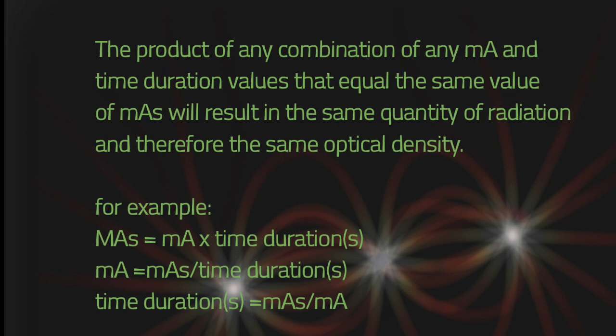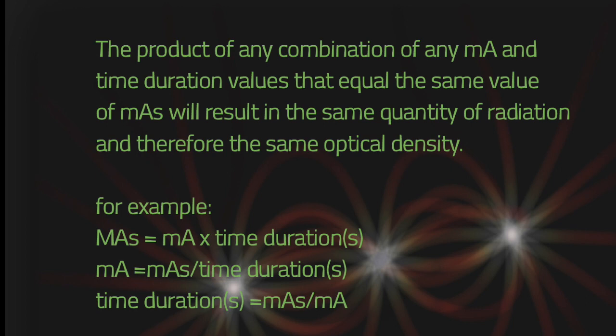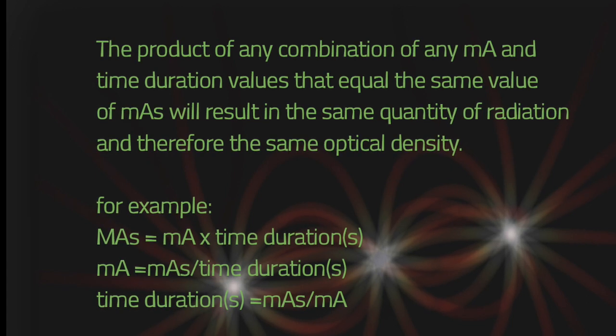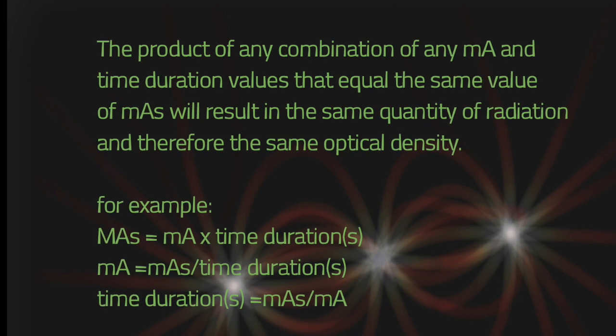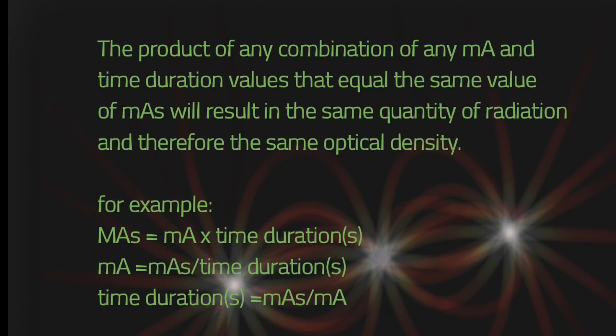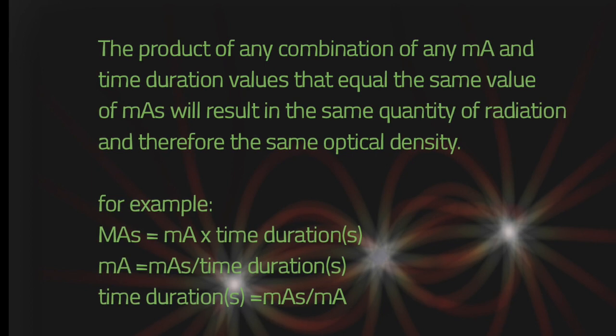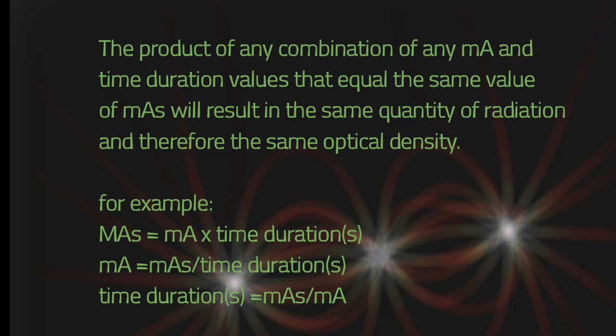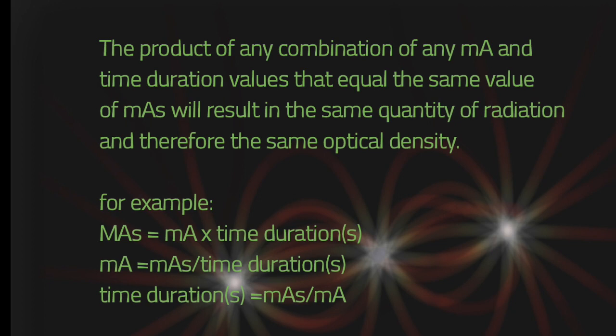Linearity of milliamperage can be evaluated using this law, keeping in mind that the quality control protocol testing and calibration should be performed for kVp output as well as quality control testing on the timer first, to ensure that milliamperage testing is accurate, as any inconsistencies in kVp and time could lead to inaccurate results obtained in testing the mAs. It should also be noted that inherent limitations with regard to instrument and equipment design will likely demonstrate some level of variation, although recent manufacturing improvements have minimized this.